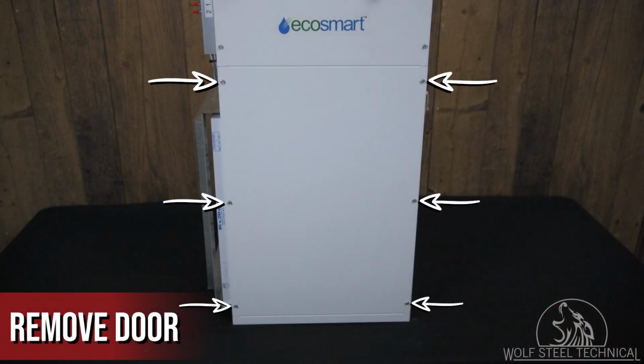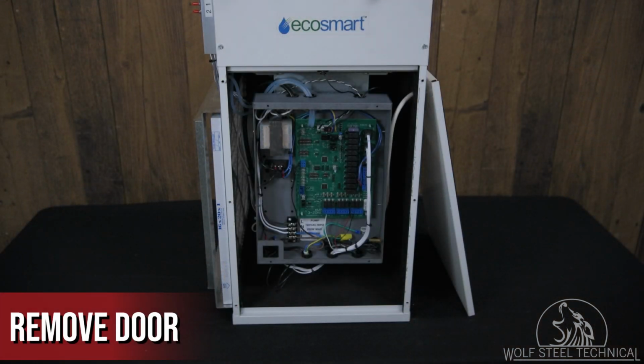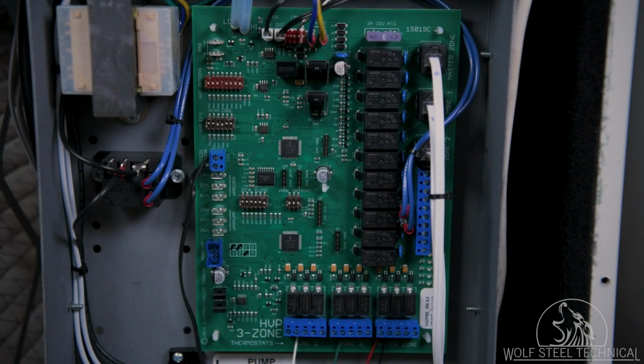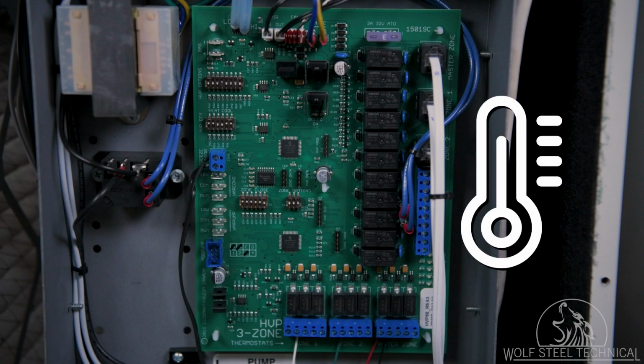Next, remove the 6 screws on the outer edge of the door to access the control board. The control board hosts many dip switches which need to be toggled to calibrate the EcoSmart system correctly. These dip switches are labeled as HVP options, HVP CFM, and zone options. There are also zone close switches, but these are set from the factory and will not be needed for calibration. First, we will look at the heating calibration for the appliance.